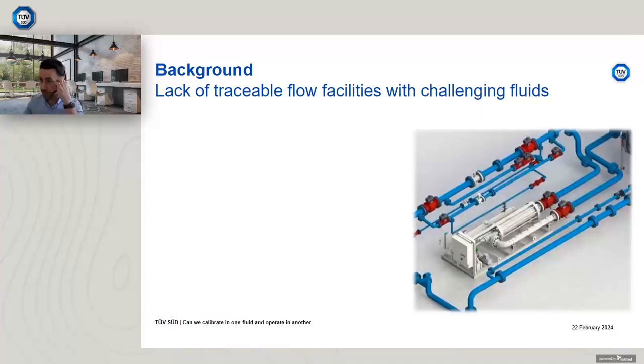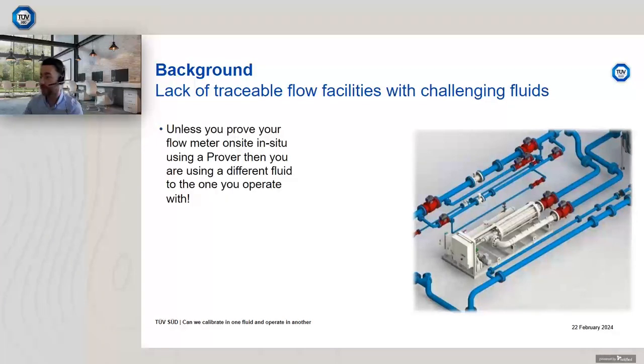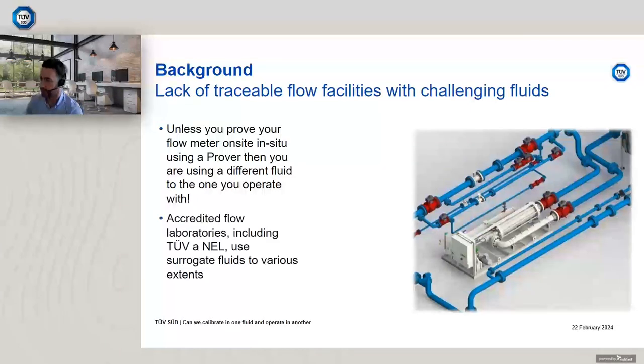So, as I say, there's a lack of traceable flow facilities. And I maybe might have said it in a joke, but unless you prove your flow meter on site in situ using a prover or a master meter, but the master meter might have been calibrated elsewhere, so there's a break in the chain there, you're potentially using a different fluid to the one you operate with. So the only way you're calibrating with the exact same fluid is if you're proving the meter on site. So anytime you send it to a calibration laboratory, you're using a different fluid.